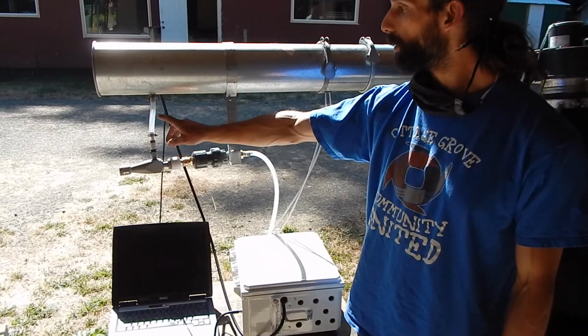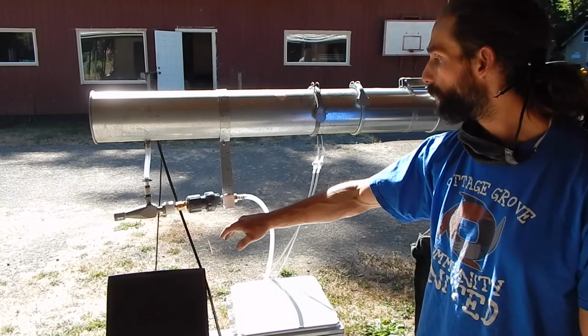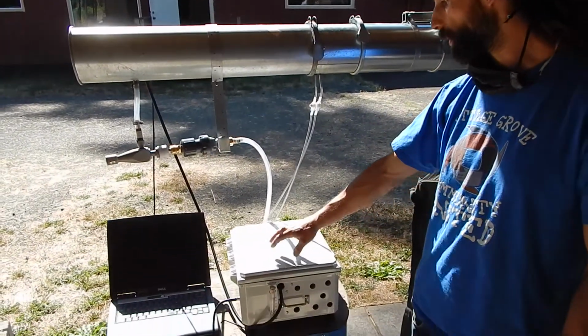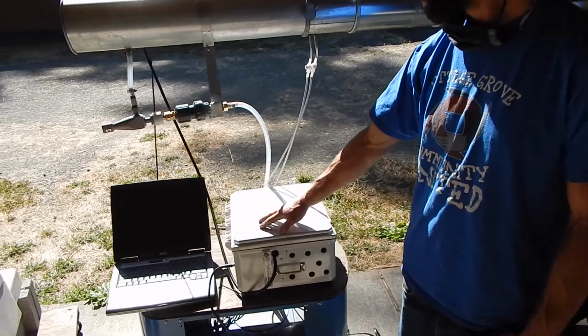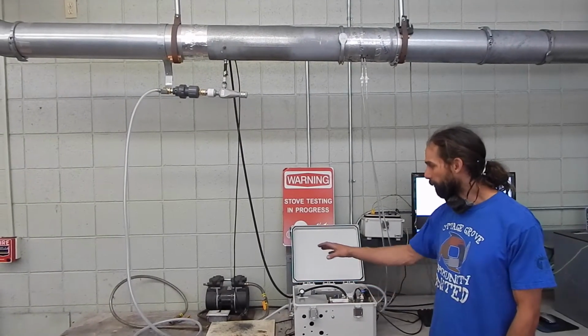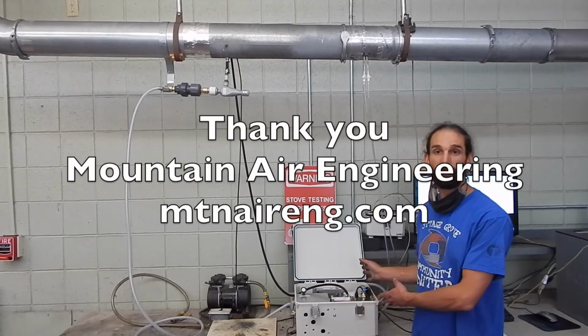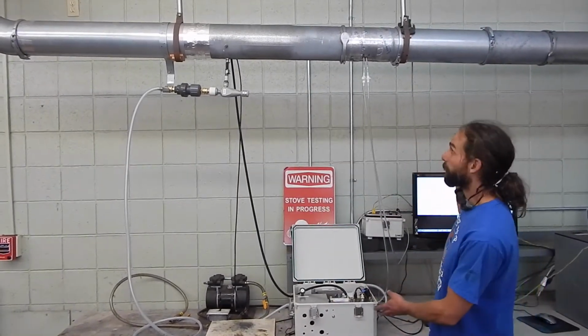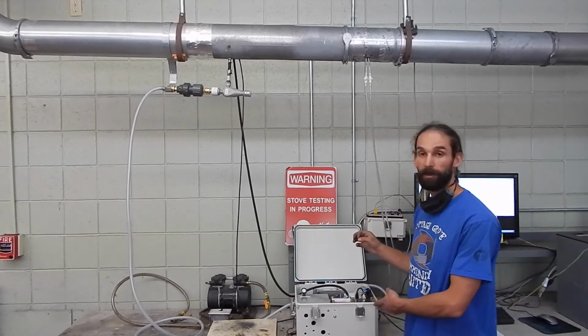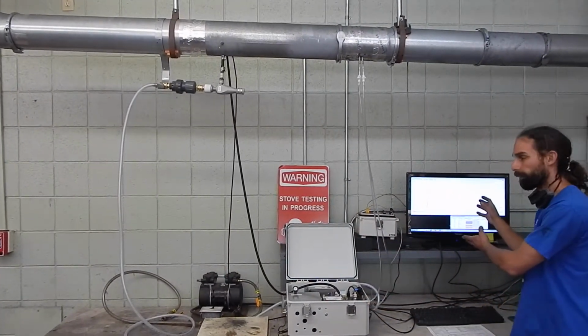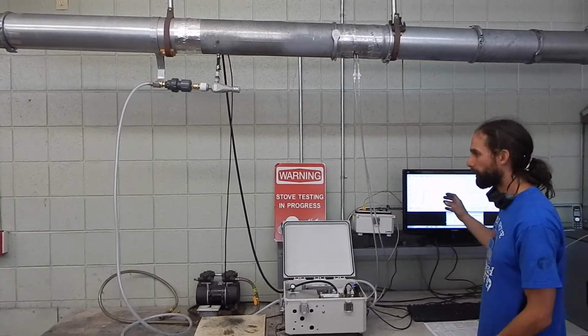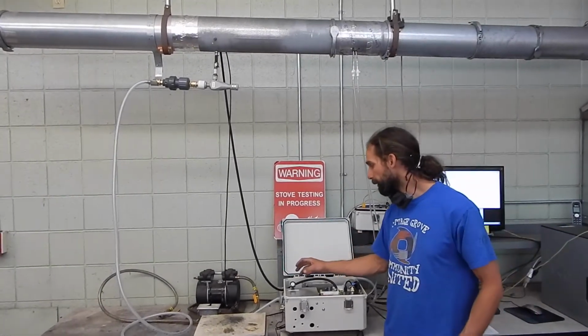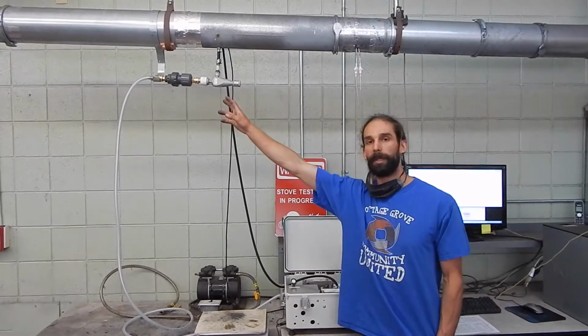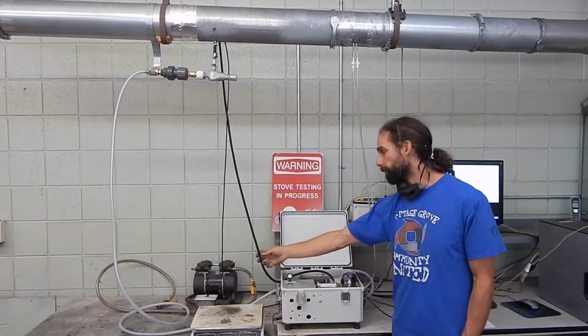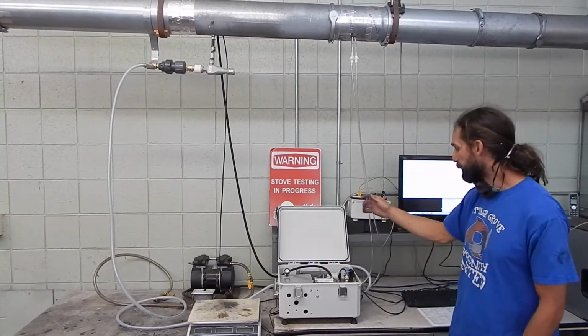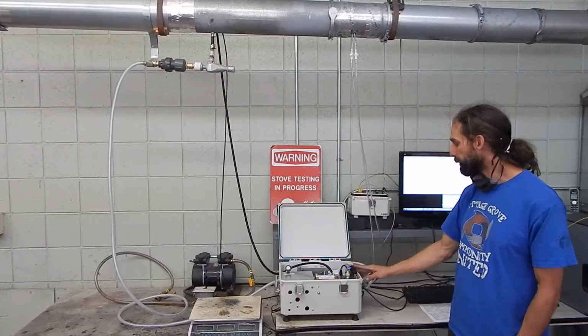And we have the gravimetric system, the same particle separator, the same filter holder, going to the now portable gravimetric system. The sensor box and the gravimetric system have been integrated into one portable unit. It's set up in front of the LEMS because it can still be used to measure the real-time emissions from the cook stove. And it can still be used to collect the gravimetric sample of PM 2.5. It uses the same gas sample line, the same pressure sensors, the same computer interface.